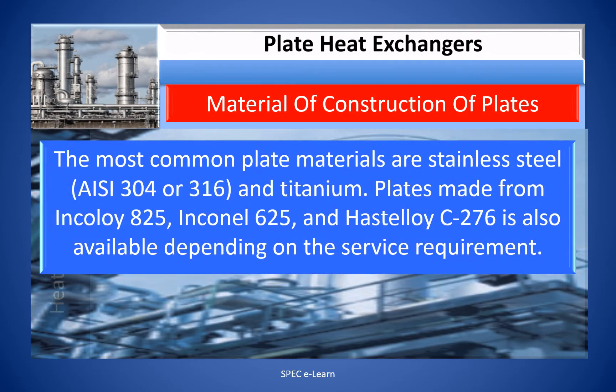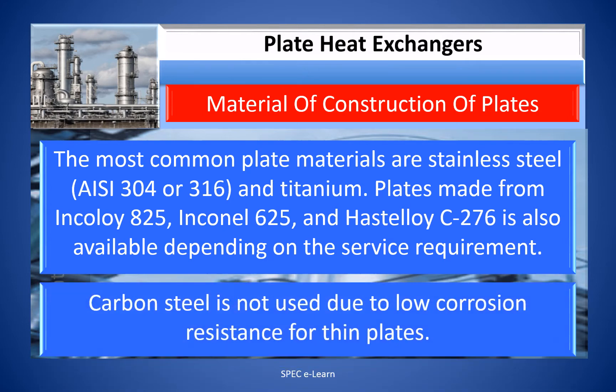Regarding the material of construction of plates: the most common plate materials are stainless steel and titanium. Plates made from Incoloy alloy 825, Inconel alloy 625, and Hastelloy C276 are also available depending on the service requirement. Carbon steel is not used due to its low corrosion resistance for thin plates.